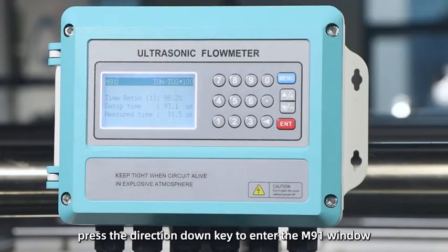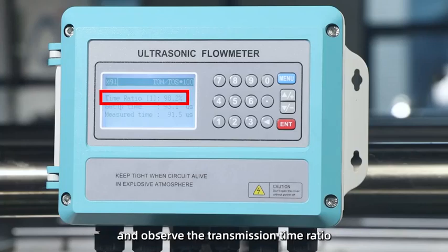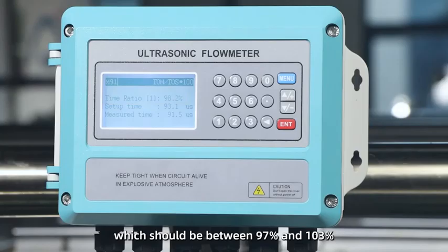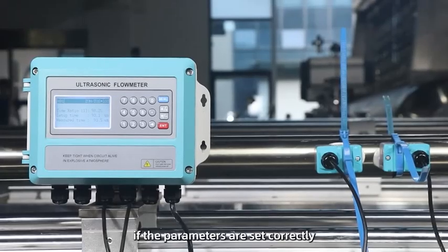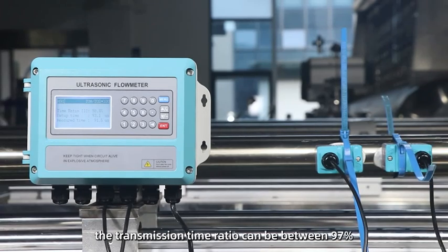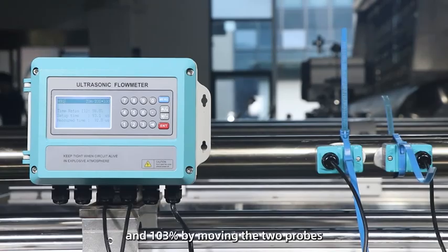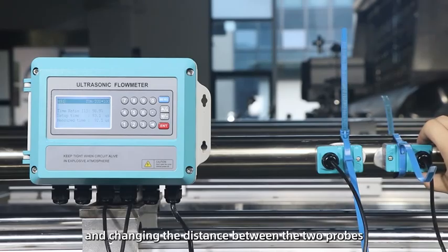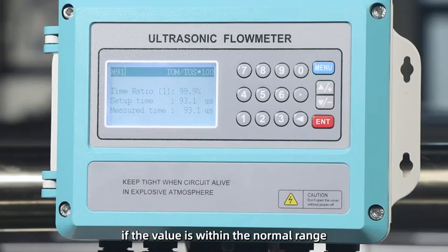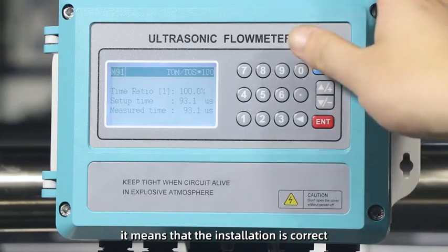Press the direction down key to enter the M91 window and observe the transmission time ratio displayed by the host, which should be between 97% and 103%. If the transmission time ratio is not between 97% and 103%, it means that the set field parameters or sensor installation distance are wrong. If the field parameters are set incorrectly, the correct parameters should be re-entered before installation. If the parameters are set correctly, the transmission time ratio can be between 97% and 103% by moving the two probes and changing the distance between the two probes. If the value is within the normal range, it means that the installation is correct.